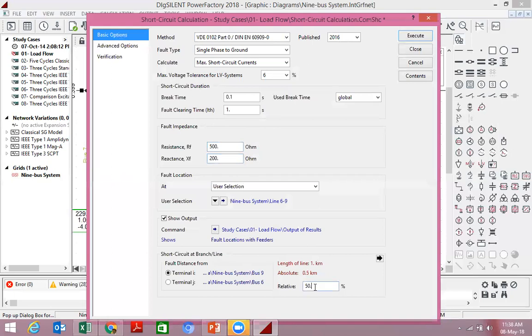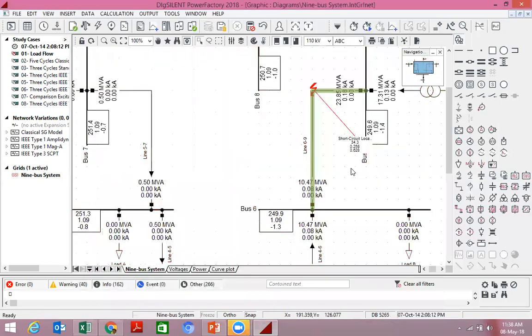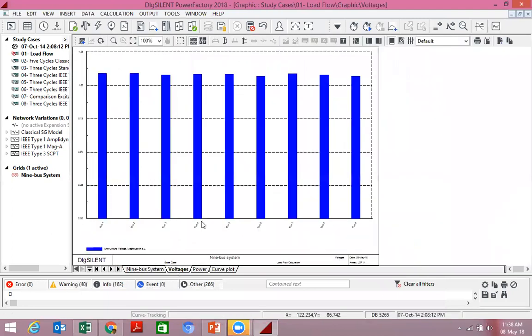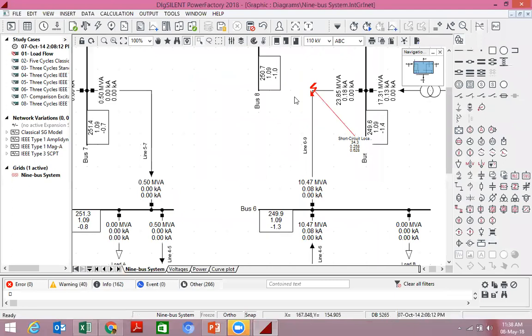And here we have the relative percentage at which the short circuit is going to happen. Before it was 50%, at the middle of the line. If you want to change that to 30 or 20%, we can change that. So just simply execute this. You will get the short circuit location, and a little bit of change in the graph, a little dip in this bus 6, but we will see more change if we change the value.